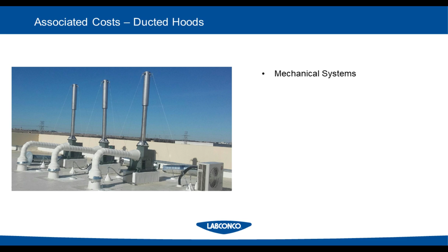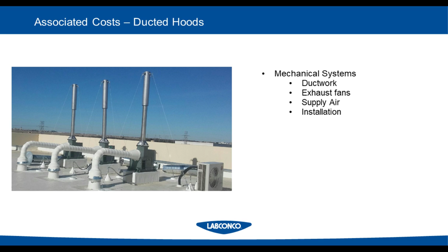So here are the associated costs with ducted fume hoods, and it mainly comes in the form of the mechanical systems. This includes the ductwork itself, the exhaust fans, the supply air, because if you are exhausting air, you need to make sure that you are supplying enough air so that the blower is able to do its job and is not starved of air, as well as the installation. So there is a lot that goes into ducted fume hoods that really needs to be thought of on the front end of the design phase, and can cause some additional costs in the build.